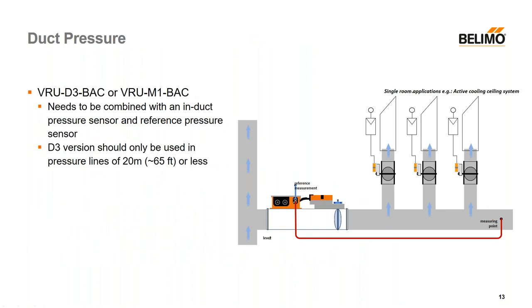Another application is duct pressure. For this we recommend either the VRU-D3-BAC or VRU-M1-BAC. You need to combine it with an induct pressure sensor and a reference pressure sensor. One important thing to be careful about is making sure that reference pressure sensor is in an area where there won't be any pressure fluctuations — if you don't, those pressure fluctuations will be transposed into your system. If you put it in a room where somebody is constantly opening and closing doors, that's going to impact what's happening in your duct, so you really want a good location for it.